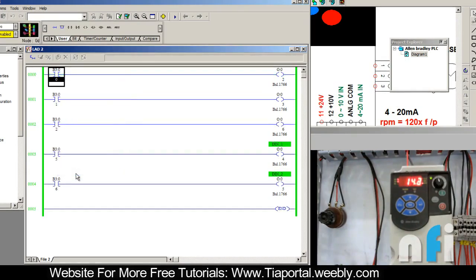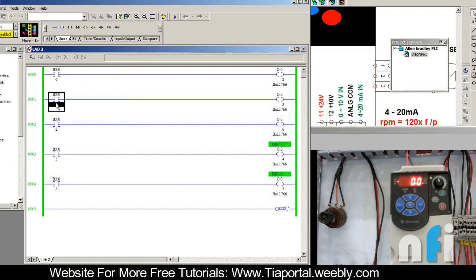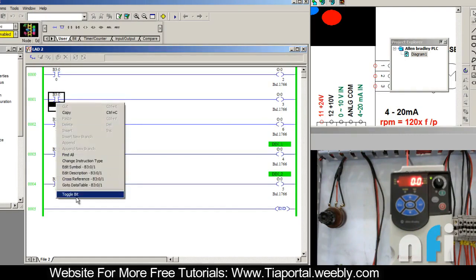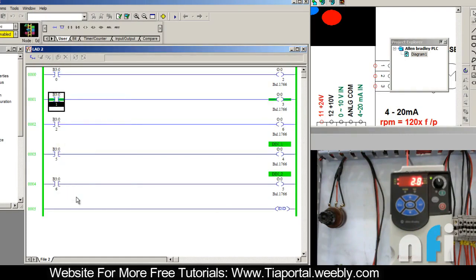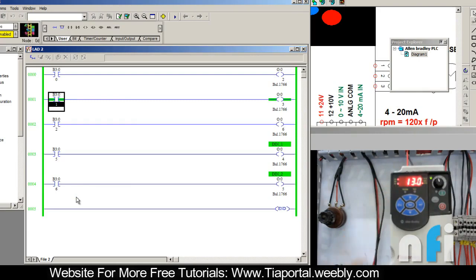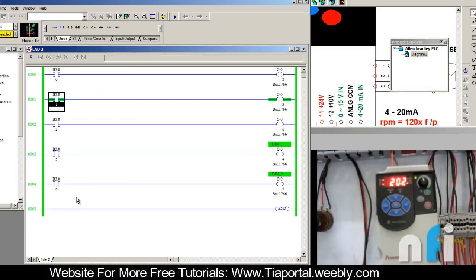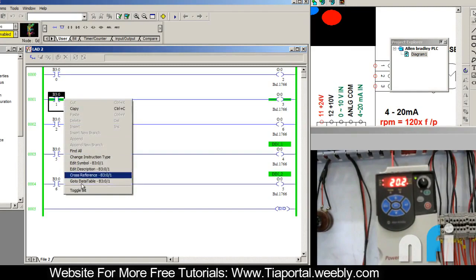It is not latched. When I go for the other one, B3, this is running the drive in reverse direction - reverse LED. That's the motor here. If I turn it off, the drive will stop.